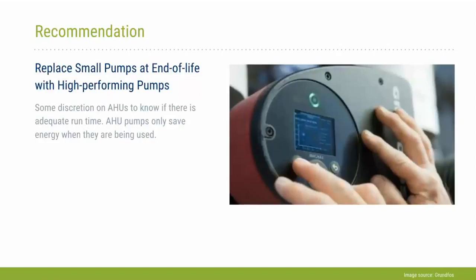And then the other piece that Jesse mentioned is that one of the huge reasons we have savings with these pumps is the varying load that exists in the building. In the case of the domestic hot water pumps, we were able to control based on the building load, looking at the return water temperature being returned to the system and getting real-time feedback to the pumps as to what's going on in the building. We were then able to throttle back the pumps and see those energy savings.